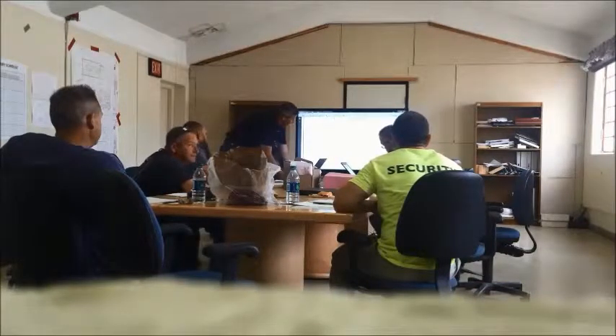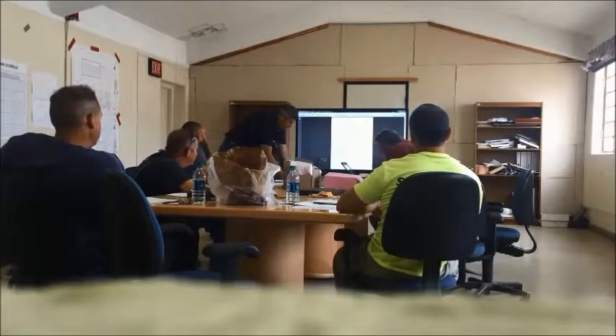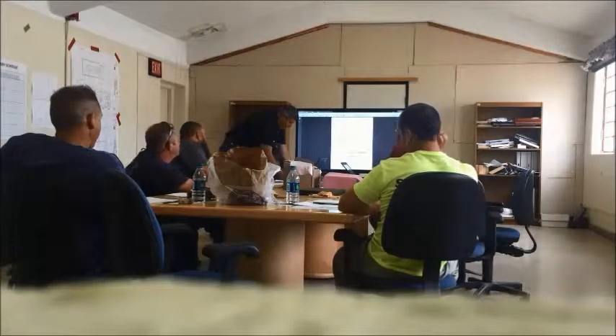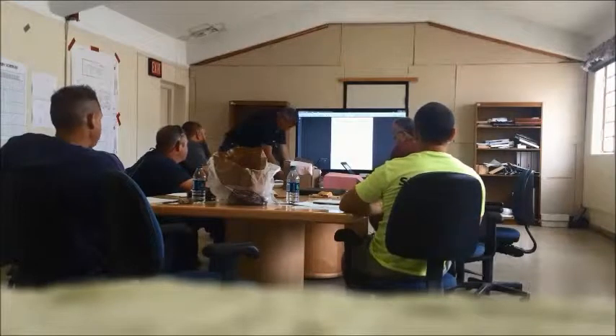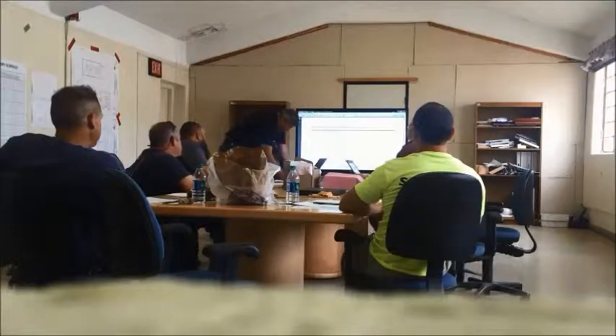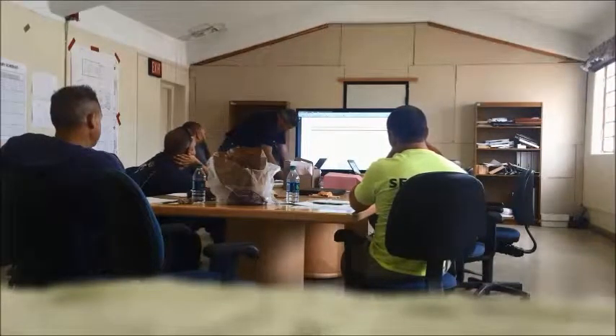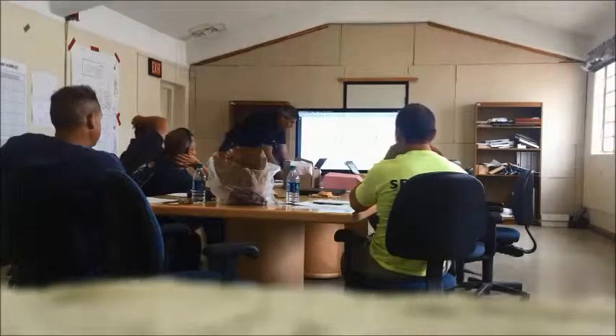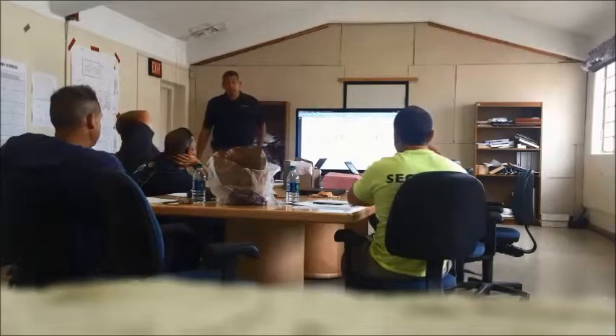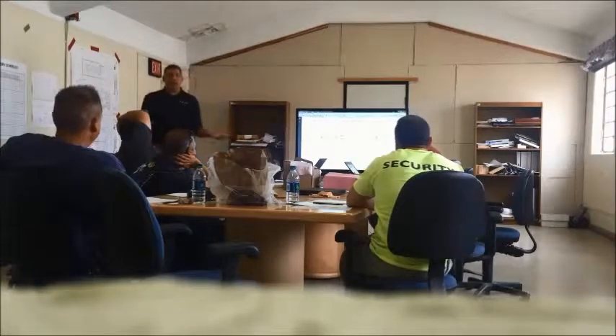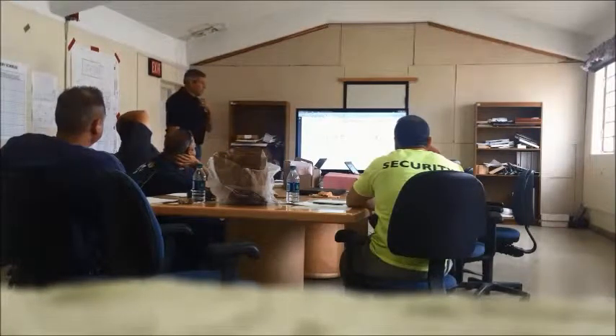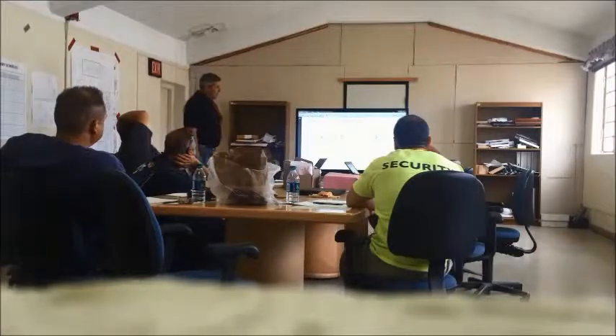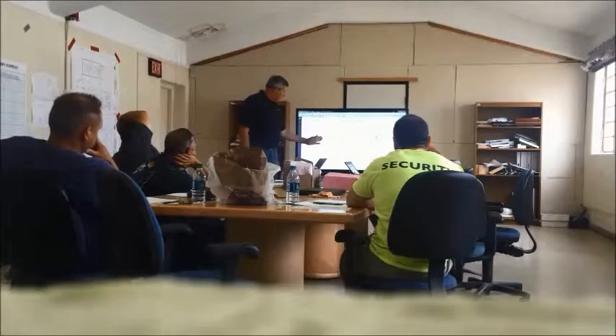Every fume hood has a monitoring panel to monitor. Give me a picture of the valve itself. Phoenix has their own controls. So there's a Phoenix controller, a Phoenix server that controls the valves. All we do on the ALC, Automated Logic, is force the commands over the network, whether it be modes, unoccupied, 4 changes, 6 changes. So this is the bellows style constant volume valve.